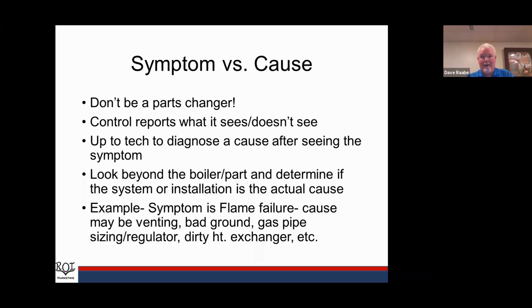Now I want to talk about what I call symptom versus cause. And when I do trainings for technicians, I always tell the guys, you don't want to be a parts changer. The idea here is you've got to find out not only what the problem is you're seeing, but what caused that problem. So as smart as we'd like to think these boilers are, and everyone says they have self-diagnostics, the control can only report on what it sees or doesn't see. And if something's not happening in the right order or doesn't have the right value, it's going to report it. From there, it's up to the technician to diagnose what caused that after he sees the symptom.